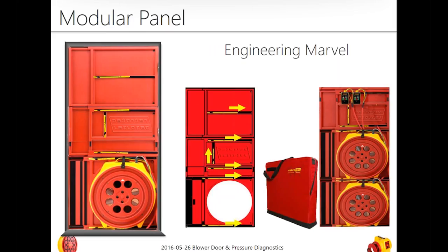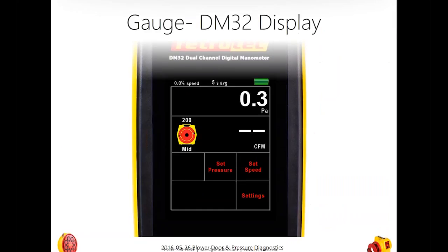If you're going to use a duct tester as a blower door, the gauge actually has a list of blower doors, and it shows duct testers in there, because Retrotec understands that when you don't have the flex duct connected to your duct tester, you have more flow and more ability to get more CFM out of it. So they have different fan curves for using a duct tester as a blower door. The answer to the question is it'll do around 760 CFM at 50 pascals, that kind of back pressure. So again, 760 CFM using your duct tester as a blower door. Thanks, Joe.